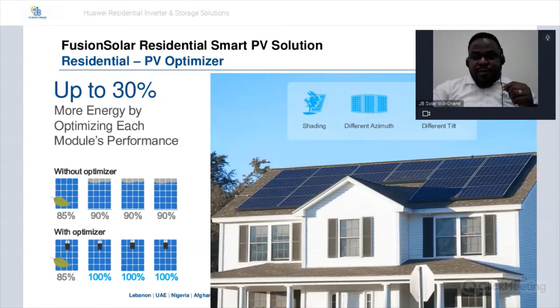You can see here, without an optimizer, once one module drops, it affects all the other modules, because the connection is made in series, meaning the same current passes through them. So when this current drops, it drops through the others too. But with the optimizer, it takes over the power qualities of the module and ensures its production is independent of the others. You can see it has boosted the energy of the other panels by about 30%. Let's take a look at other instances.